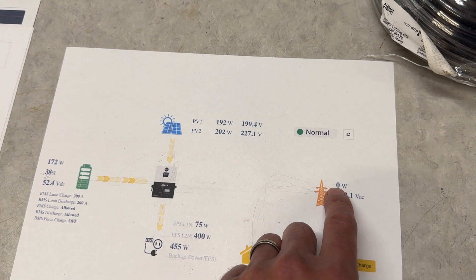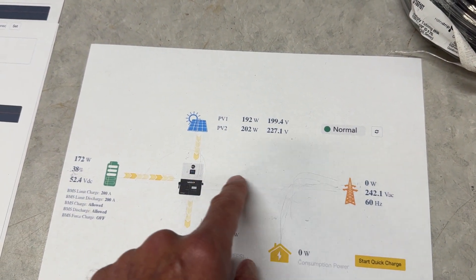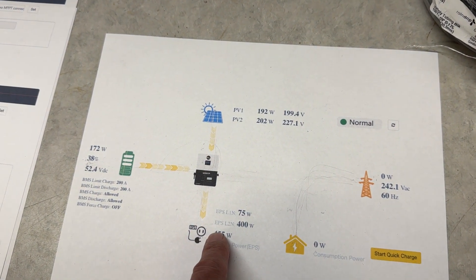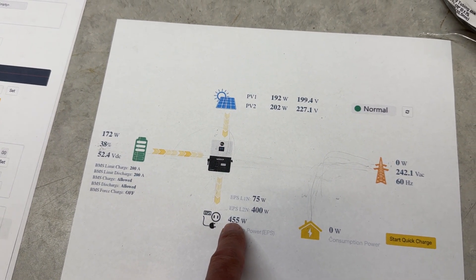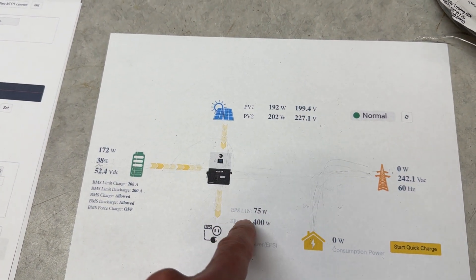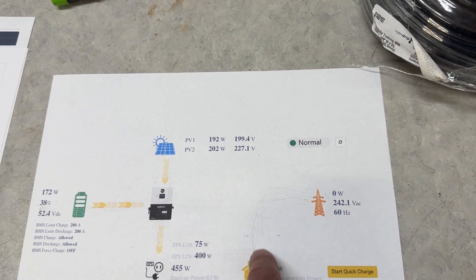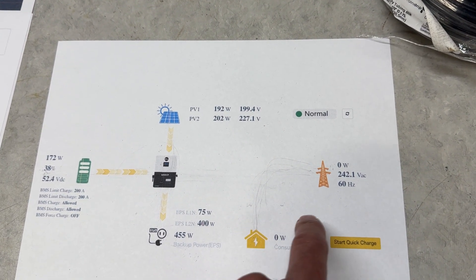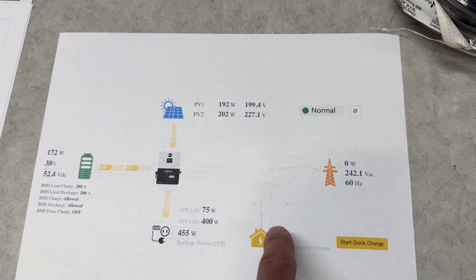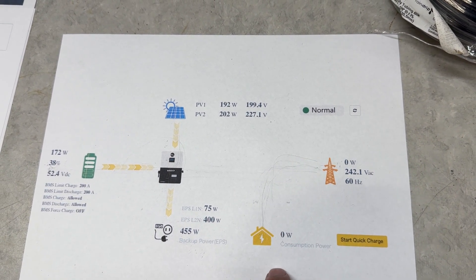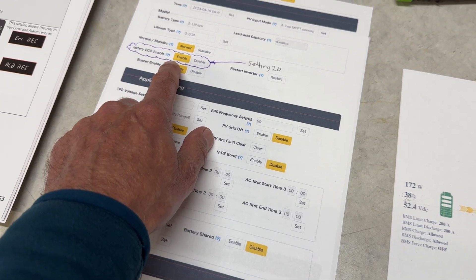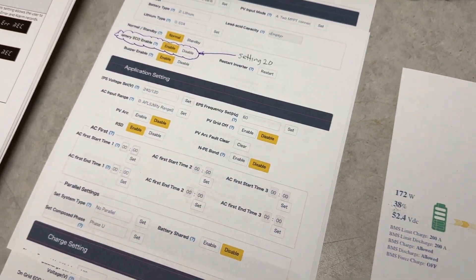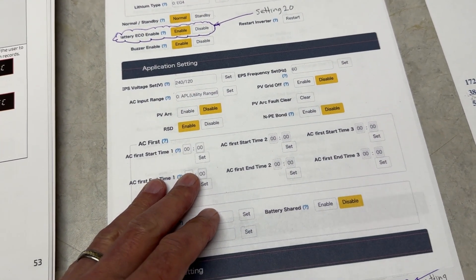The reason why that's important is when the grid goes through the inverter and out to your house, there's a loss inside here. So if you see a thousand watts going in from the grid, you might only see like 950 or 920 watts going out to the house. By having grid bypass, if you have a thousand watts here, you've got a thousand watts here—there's no loss. So that's why this setting is important.